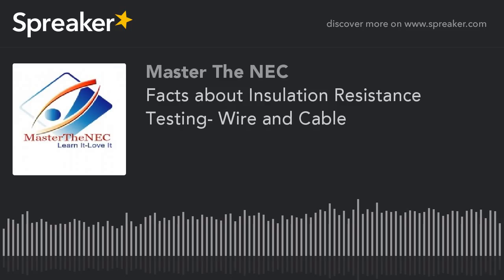That's fine. But the general rule is, if I'm connecting insulated conductor to insulated conductor and I'm getting readings anywhere from the 2 to 99 megaohm range, I don't necessarily say that it's bad. It could be due to contaminants, different things that are on the wire, the temperature, the humidity, how long it was installed. It could be the length, the distance. You know, I routinely get calls about 5, 6, 7, and 8,000 foot runs of wire. Okay, the longer it gets, the more potential current leakage, because you have more opportunity, more surface area to do so. However, if you don't provide a reliable path to take those readings, then the results are going to be kind of skewed. So what is the true shining light of a megohm meter when it comes to wire and cable? And let's talk about that.